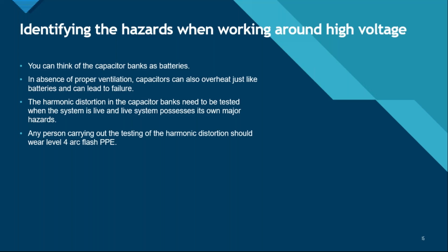With capacitor bank testing, with harmonics testing, the inspector needs to check the harmonics on a live system, right? You cannot really isolate the capacitor bank to check the harmonics. It should be a live system. So that has its own hazards.